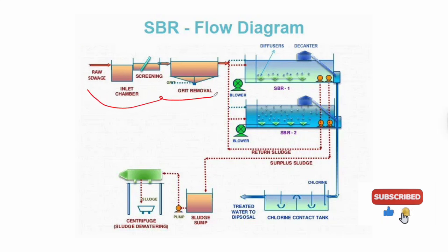Before reaching the SBR, wastewater undergoes pre-treatment. This typically includes screening to remove large particles such as branches or big stones, followed by grit removal to remove sand, grit, and other coarse material that could damage mechanical equipment like pipes and mixers.